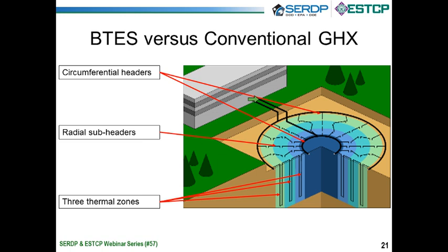So what I just illustrated would be discharging of the BTES, the warm water hitting the perimeter and being able to dissipate its heat to infinity, if you will, beyond the bore field. And then we're chilling the water three different times through these boreholes and colder water passing back to the building, nice cold water that the chiller can use for very high EERs or low kW per ton.